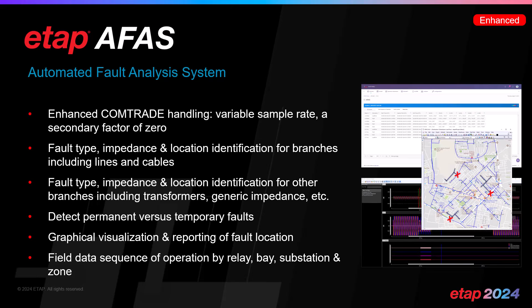With AFAS, beyond fault analysis, we can now examine the ComTrade file and determine, based on detection logic, whether we're dealing with a fault, a voltage dip, motor start, motor stop, or motor acceleration—by detecting the pattern and combining that with the digital twin to resolve differences when reading the ComTrade file, whether it's a fault event or an abnormal disturbance of a different nature.